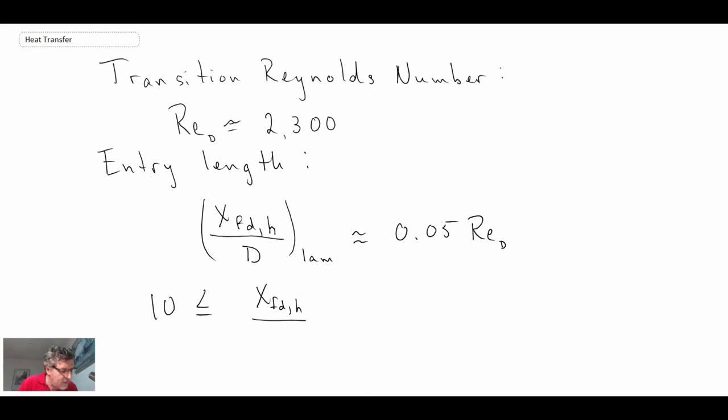To get to fully developed flow for the hydrodynamic flow field, rule of thumb is between 10 and 60 diameters. That's how long it will take to get to fully developed flow for turbulent flow fields.